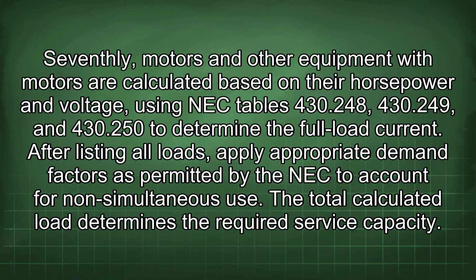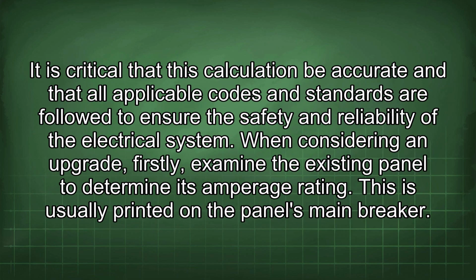After listing all loads, apply appropriate demand factors as permitted by the NEC to account for non-simultaneous use. The total calculated load determines the required service capacity. It is critical that this calculation be accurate and that all applicable codes and standards are followed to ensure the safety and reliability of the electrical system.